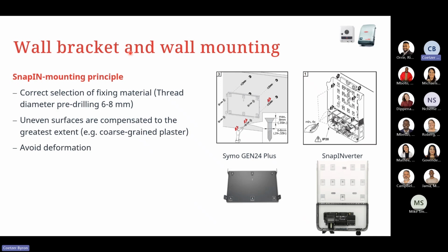So again, for your wall bracket and wall mounting, this is referring to our snap-in mounting principle or concept that we have. So the correct selection of your fixing materials. Either use 6 to 8 millimeter pre-drilled rawl bolts or fischer plugs to hold the units in place. And then uneven surfaces are compensated to a greater extent. So just make sure that you avoid any deformations, both on the Gen24 and SNAP inverter plates, simply because if we have a deformation on the SNAP inverter side, we would then be at risk of not being able to mount correctly, either on the DC side or on the AC connection point when the unit snaps back into place.